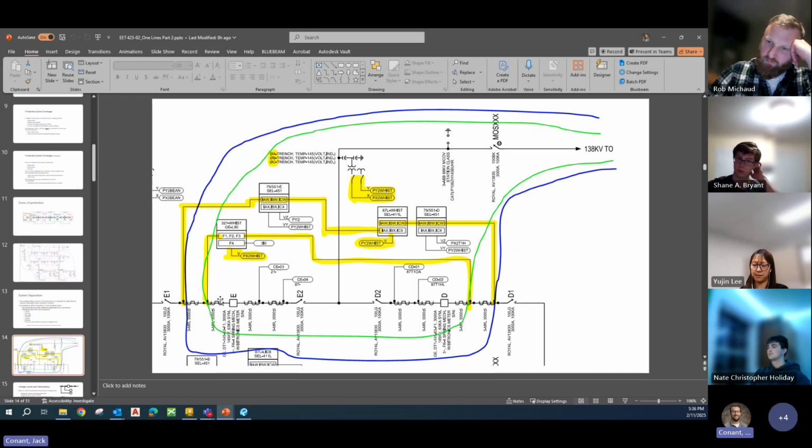And you can see, like I was trying to explain, one system will tie into this set of CTs on the inside, and then the other system will tie into the outside set of CTs on the breaker. And it looks like they have a GE L90 relay for one system and an SEL-411L relay for the other system. But again, like I was saying, sometimes these are the exact same relay doing the exact same function, exact same protective schemes, and it's really just for redundancy.